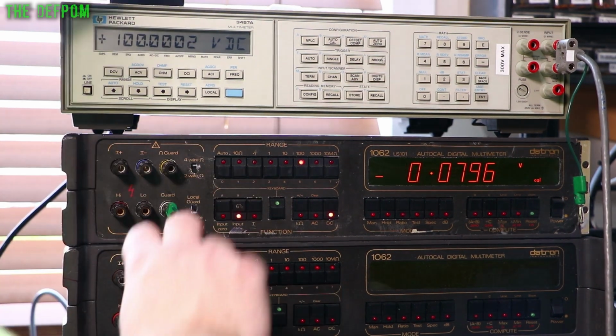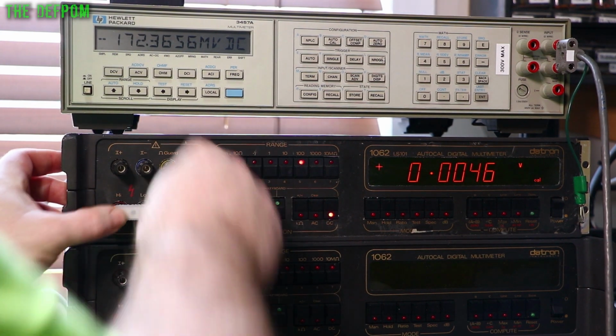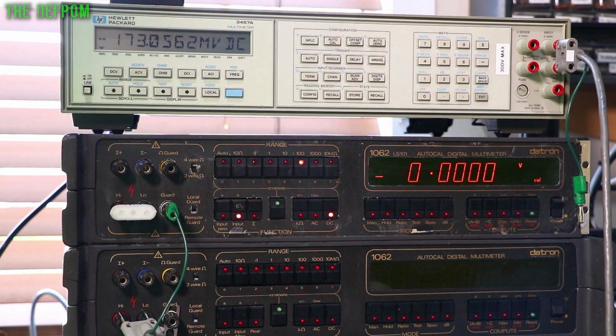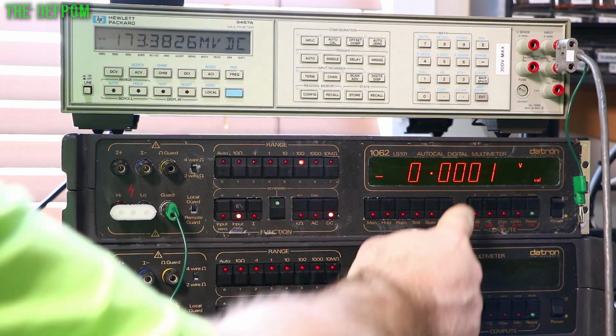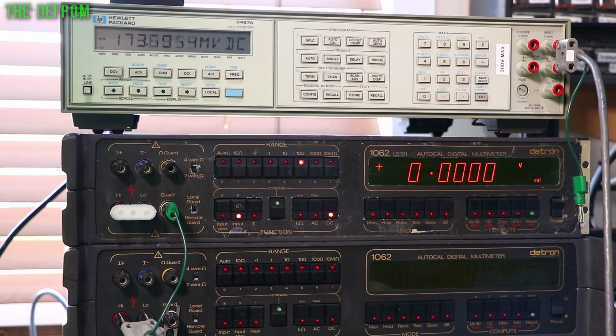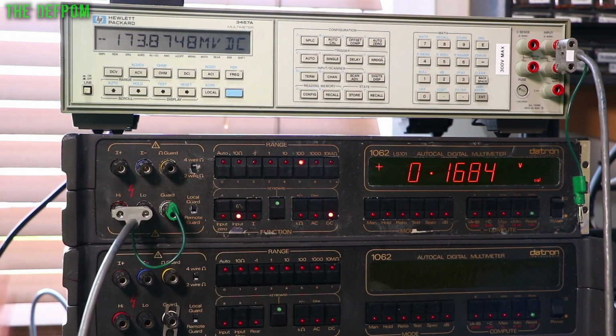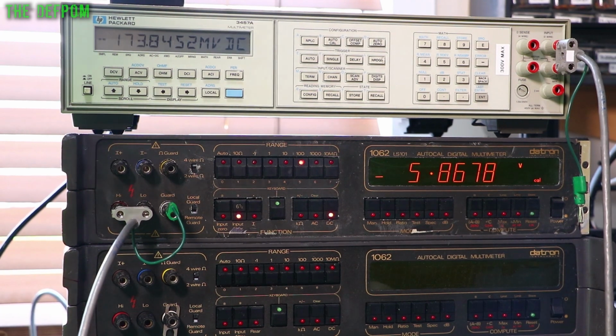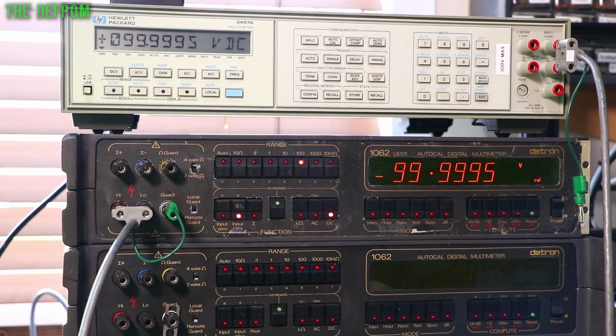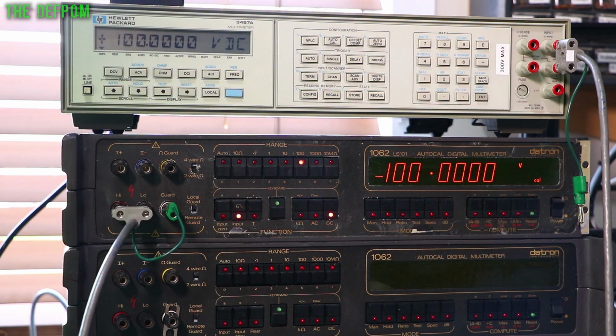Shut the calibrator back off. Check the zeroing. Hit 0 again. Reverse polarity. Turn the calibrator back on. Let it settle again. And that's actually looking really good. I think I don't have to do anything there. It's bang on. That's absolutely fine. So cool. So that's up to 100 volt range done.